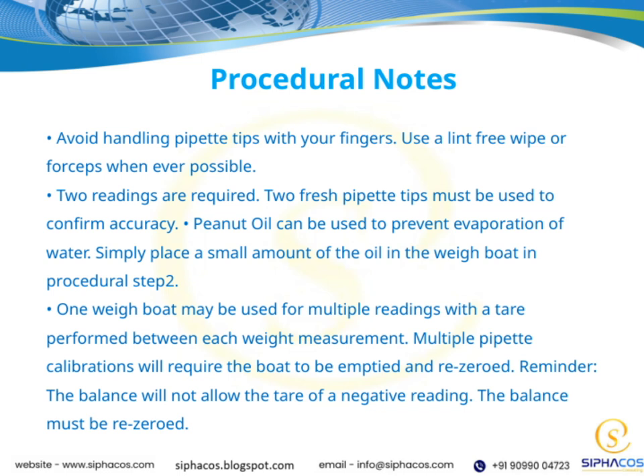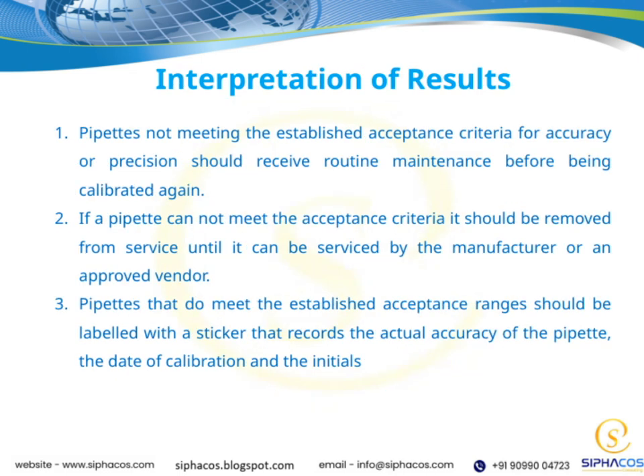When a pipette doesn't meet the established acceptance criteria for accuracy or precision, it's important to perform routine maintenance before attempting to calibrate it again. This helps ensure it's operating correctly and can deliver reliable results. If a pipette consistently fails to meet these criteria, even after maintenance, it should be removed from service. In such cases, it needs to be serviced either by the manufacturer or an approved vendor to address any underlying issues. On the other hand, if a pipette does meet the acceptance ranges, it's good practice to label it clearly.